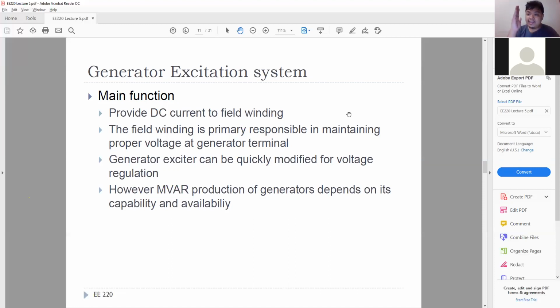But when it's not at full capacity, it also changes, not 0.8, 0.6. Sometimes it can be at a range of 0.4 to 0.2. It depends, obviously different generators have different capabilities. So its MVAR capability is very limited depending on its megawatt output. It can't sustain very high MVARs.